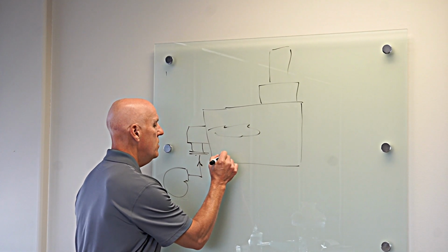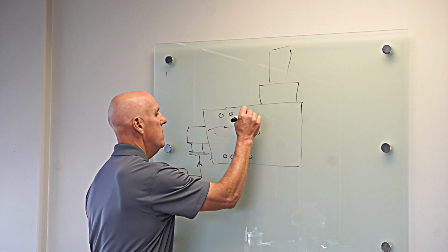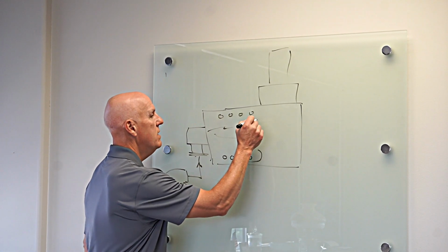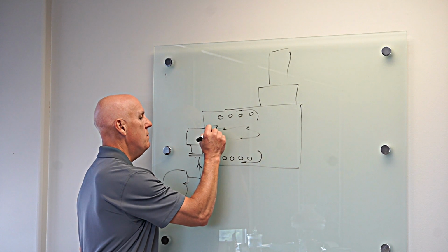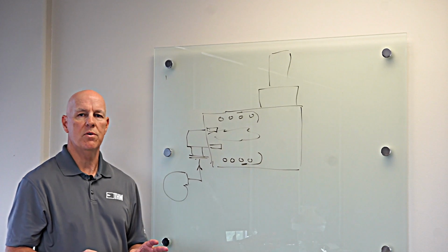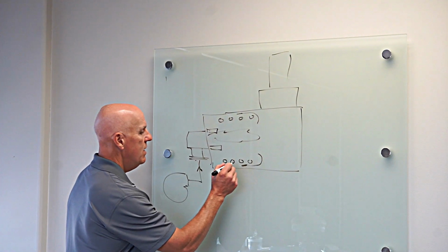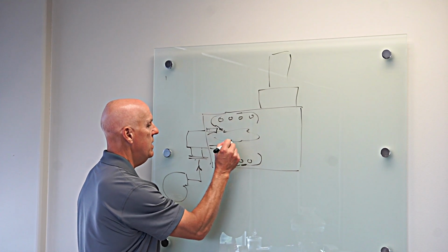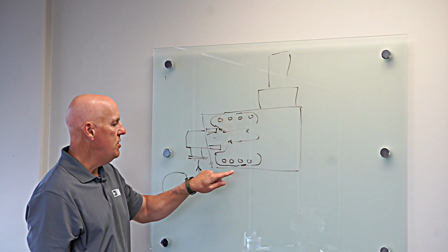If I design a heater where I've got the coils spaced in here in such a way that it allows for gases to come back this way, then possibly I can buy a burner that actually makes that happen. There are burner styles out there called internal flue gas recirculation. So you can buy a burner and design the heater to accommodate that, and it will actually draw this flue gas back up into the flame, okay?